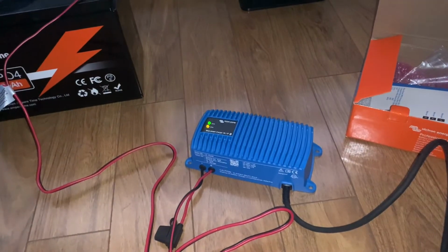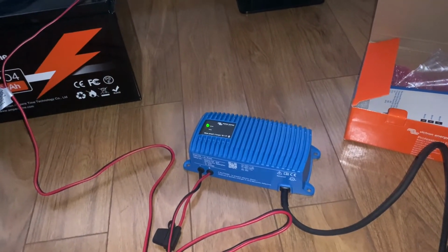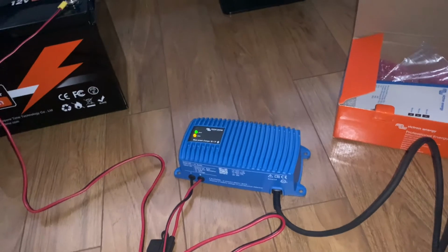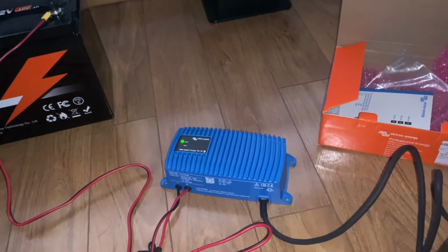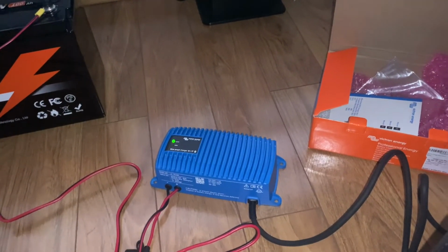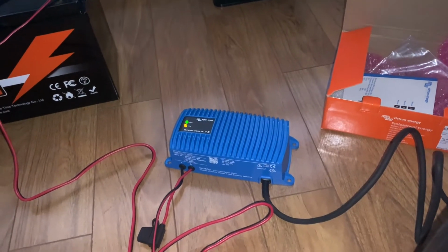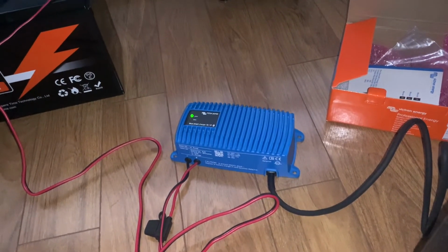We're in absorption now, and it's wanting to document that we can definitely see the little orange light is blinking a heck of a lot slower. Just for my records now, I can see the difference between the speed of the beep, and this would tell me we're in absorb.